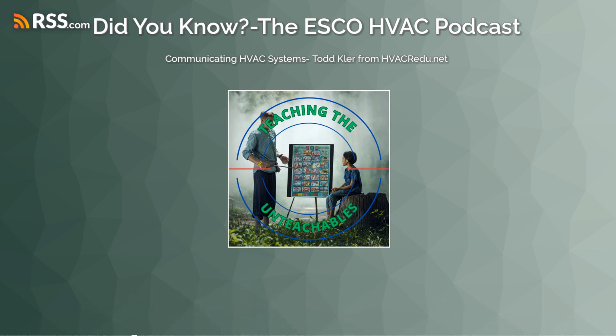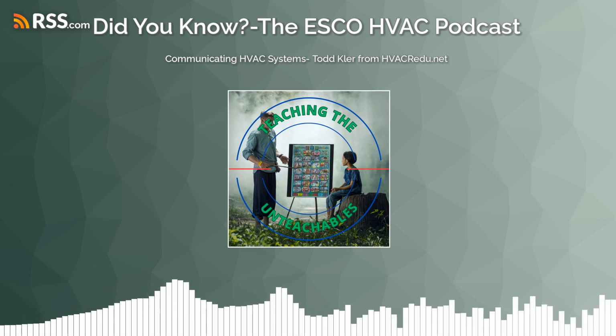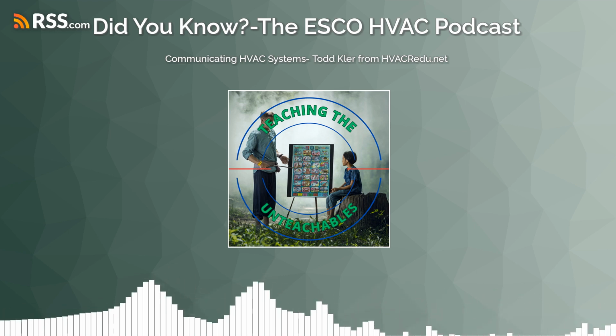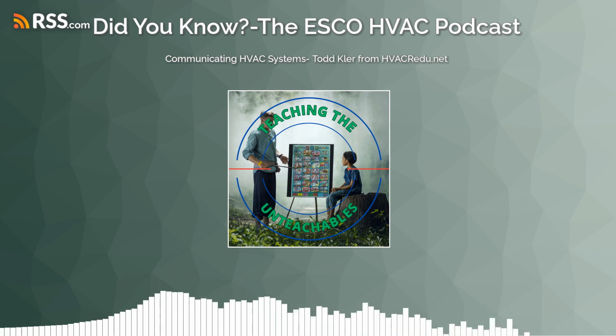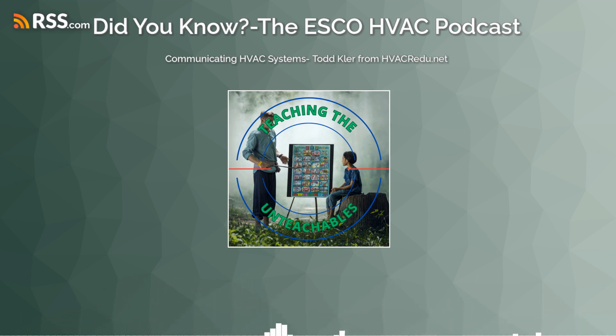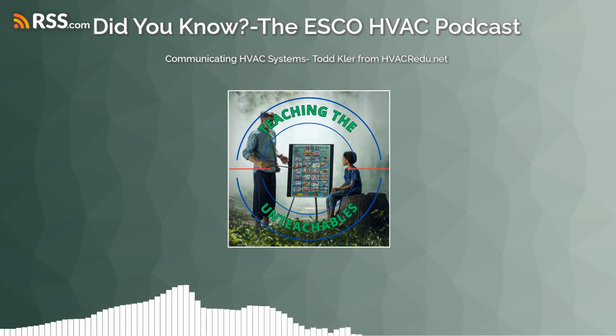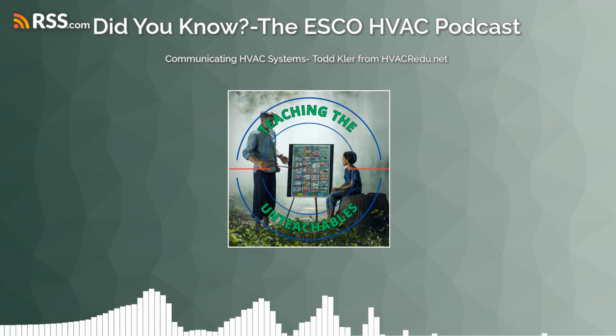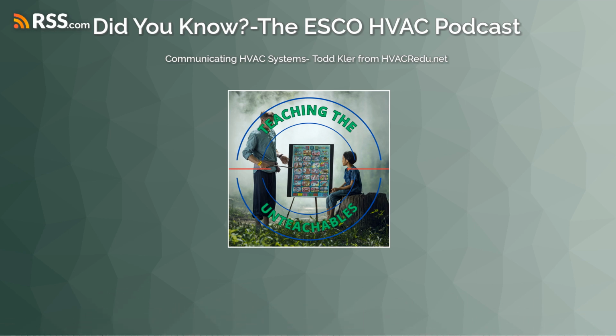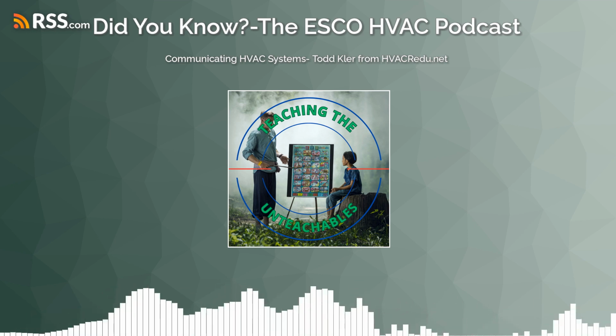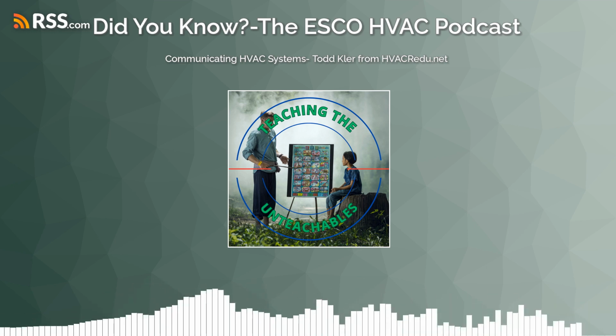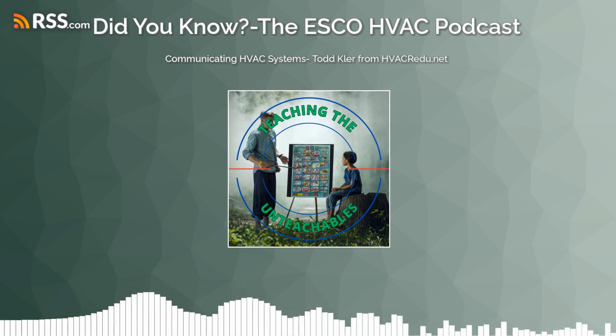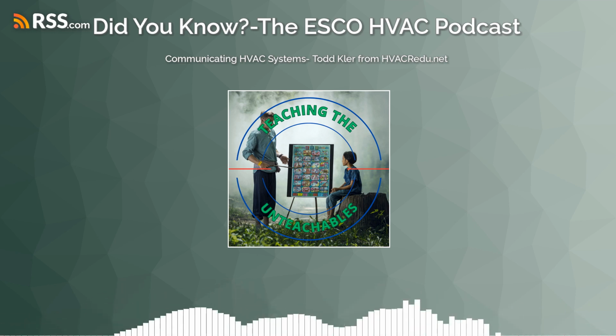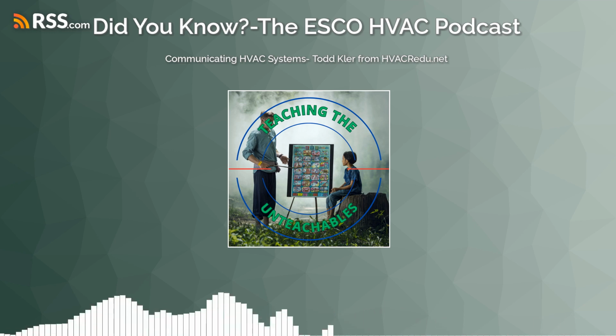Let's look at Comfort Sync, right? Let's look. You think this might look similar to Lennox? Well, look at that. I'm seeing common, I'm seeing R, I'm seeing positive, and I'm seeing negative again. And look at our pseudo shielded cable with our typical 18 gauge whatever. Yeah. So if it's a non-communicating wire, we got communicating existing wires. Boom. We're going to tie those together. And then we're going to check our voltages, right? The service instructions are a tad bit different, because of the communicating platform that they're using. What we're checking changes. How we check it never actually changes.